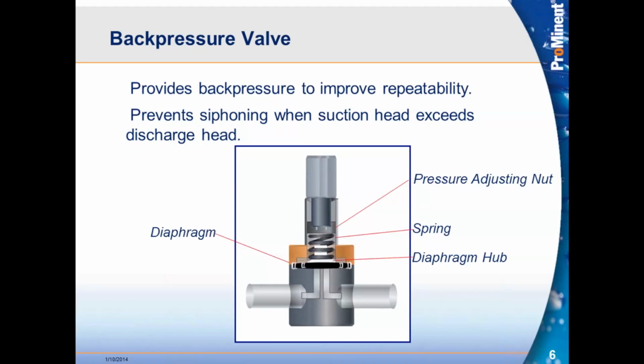You can see the diaphragm indicated. Then we have a spring above that, and we have a diaphragm hub. That diaphragm hub takes it so that spring isn't pushing directly on the back of the diaphragm. So now the force required to open that diaphragm is our pressure that we're going to generate with the pump. So now it has to push against that spring. To make it require more pressure, we're going to want to pre-compress that spring. So to do that, we simply adjust that adjustment nut down further.